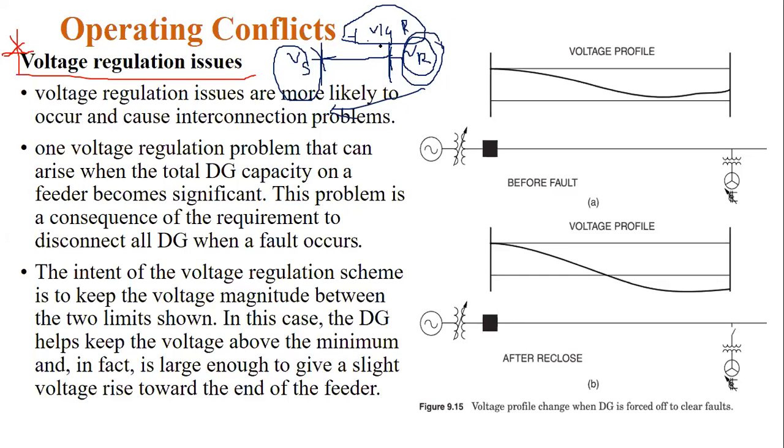So where you can get the lower voltage levels, for example, VS minus VR. Suppose VS is 130 volts and VR is 120 volts. Then what is the percentage voltage regulation? Nearly 10 divided by 120. This is the gap. A 10% voltage gap is there.